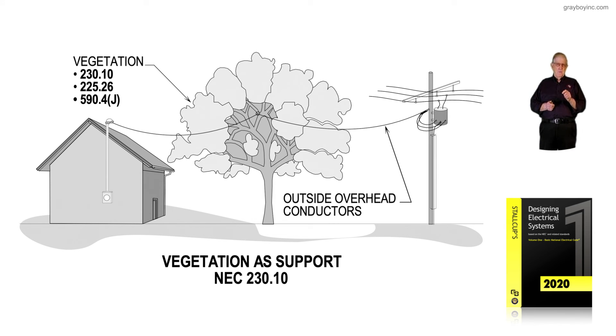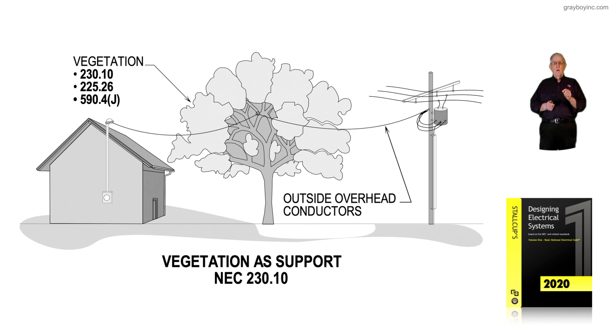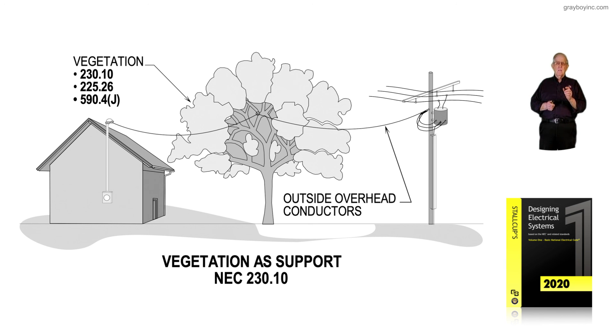To get a good handle on this, read and review 230.10 for services. For feeder conductors, refer to 225.26. For construction purposes, go to 590.4(J) and search out these requirements based on whether it's overhead service conductors or overhead feeder conductors used for construction purposes. Figure 6-11 basically deals with vegetation used as supports in accordance with 230.10, which is prohibited.